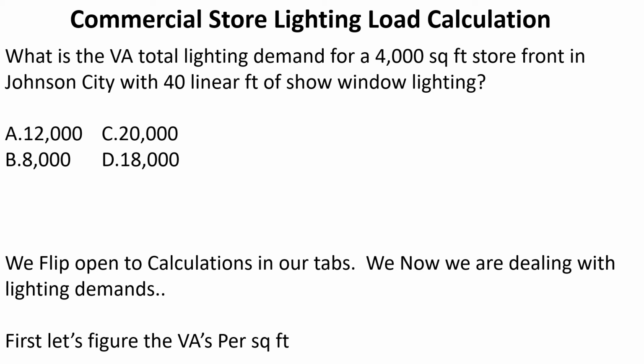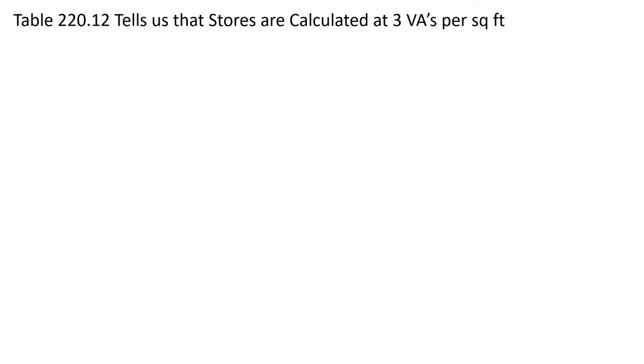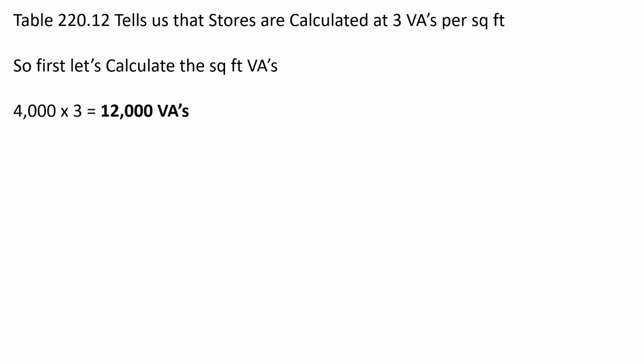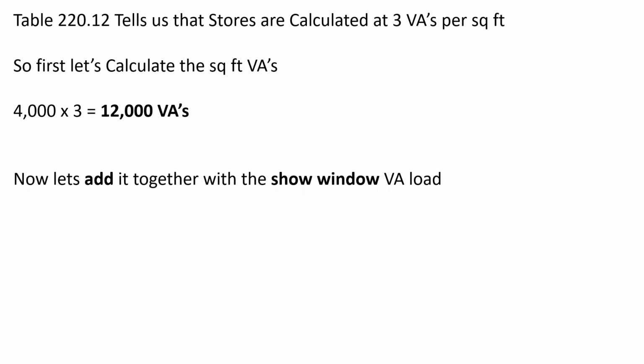What is the total VA lighting demand for a 4,000 square foot storefront in Johnson City with 40 linear foot of show window lighting? We flip open our calculations tab. We know that we're dealing with lighting demands. First, let's figure our VAs per square foot. Table 220.12 tells us that stores are calculated at 3 VAs per square foot. So first, let's calculate the square foot VAs. You take 4,000, multiply by 3, and you get 12,000 VAs. Now let's add it together with the show window lighting VA load.